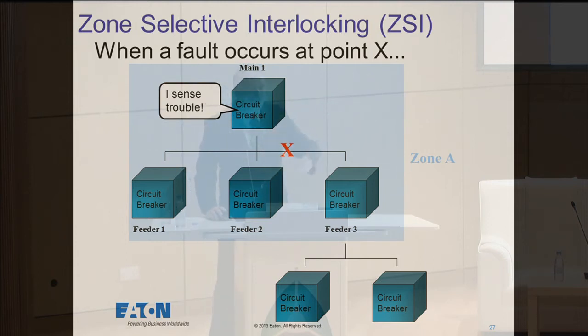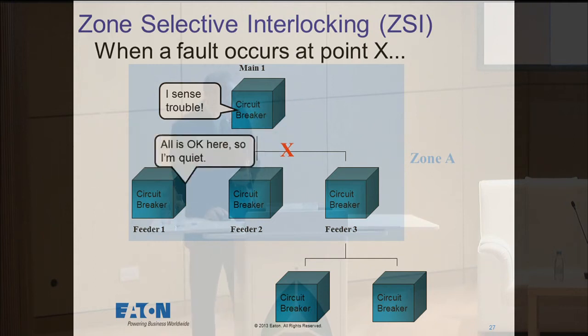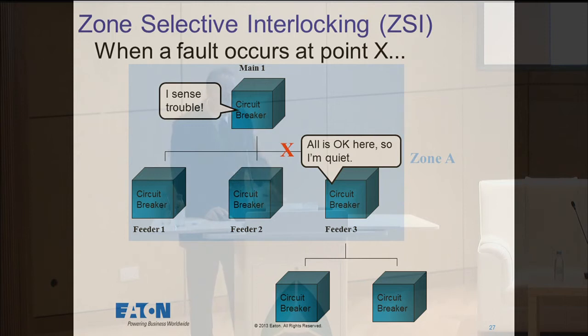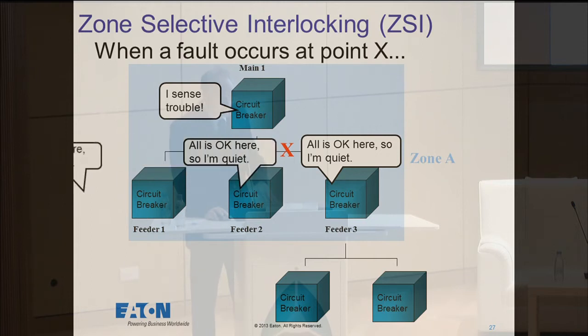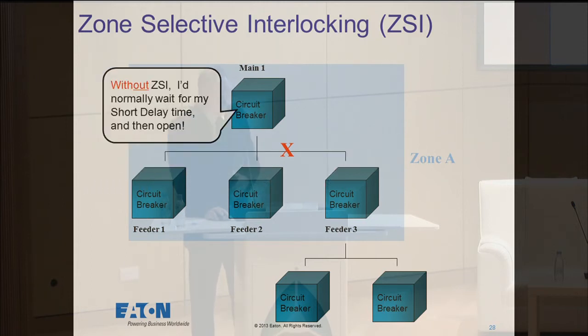They use digital communications, so they're not audibly saying, I sense trouble. But he is picking up that there's a fault downstream from him. This one here, he doesn't see anything. It's on his line side, so he doesn't do anything. The same with that one, and the same with that one. So without zone selective interlocking, he's normally going to wait for his short delay time until he opens, because he's trying to be coordinated with the breakers downstream. So he's set for a half second. He would normally sit there and wait.